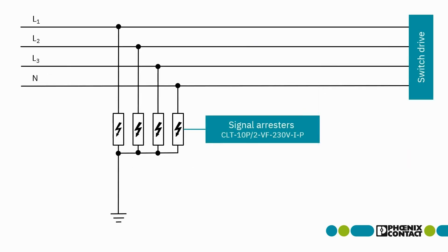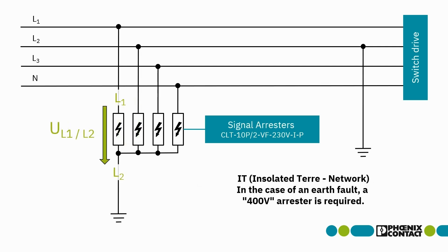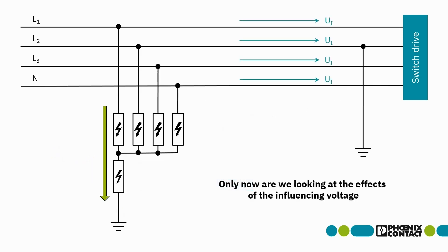Here is a practical example. First, without influencing voltage: in normal operation, the interlinked voltage of 400V is applied via two arrestors. In the event of an earth fault, the earth potential assumes the L2 potential, resulting in 400V at the arrestor. However, a 230V arrestor is not designed for this load capacity. As a measure, another arrestor — the summation arrestor — is integrated. Now the interference voltage should also be taken into account.